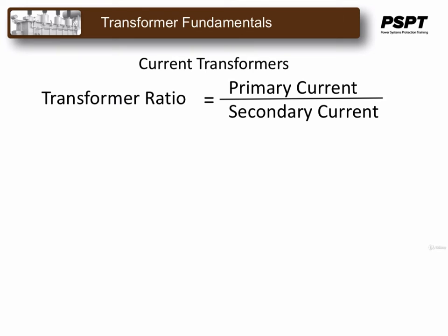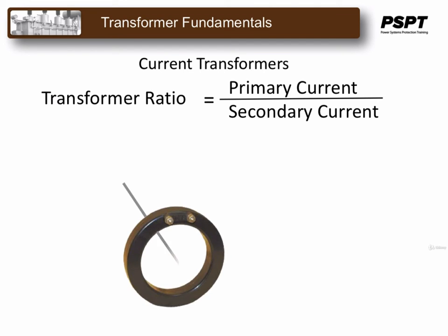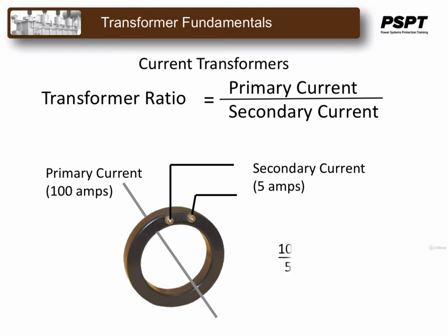The transformer ratio of a CT is usually designated by stating the primary current versus the secondary current, and the stated secondary current is usually the rated secondary current of the CT. For a given CT where the primary current is 100 amps and the secondary current is 5 amps, the transformer ratio is 100 over 5, or 100 to 5, or 20 to 1.